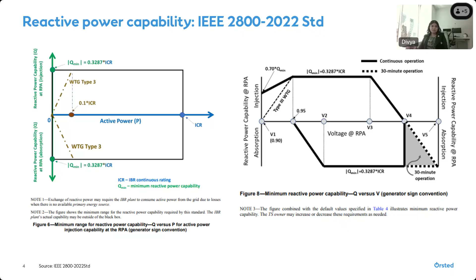But today, if we go back and ask the vendors and equipment manufacturers, typically at type 3 you may not get any reactive power output at zero active power, while for others you may get full capability. You could also define it in terms of voltage, as done in the 2800 standards. So it's important to recognize that most of this was a compromise based on the technology type the plant uses, not necessarily just the grid needs.